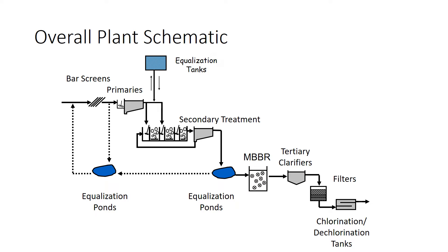The 67 million gallon a day plant treats wastewater in a series of steps with enhanced biological nutrient removal (BNR) and advanced wastewater treatment (AWT), achieving nutrient limits of 0.18 mg per liter total phosphorus, 1 mg per liter of ammonia nitrogen, and 3 mg per liter of total nitrogen. Planning has begun for the expansion and rehabilitation of the secondary treatment process, which removes nitrogen to 5 mg per liter and phosphorus to about 0.5 mg per liter.